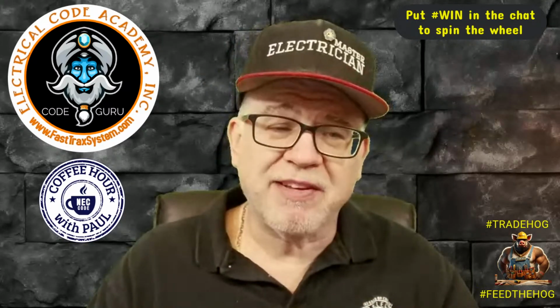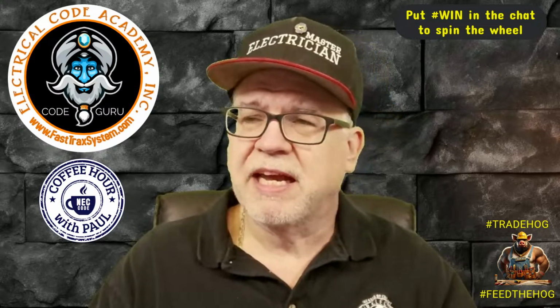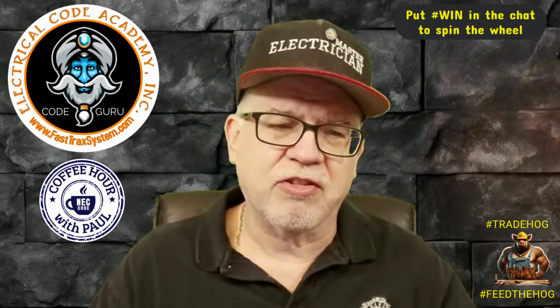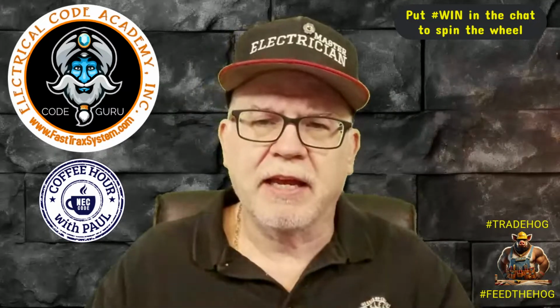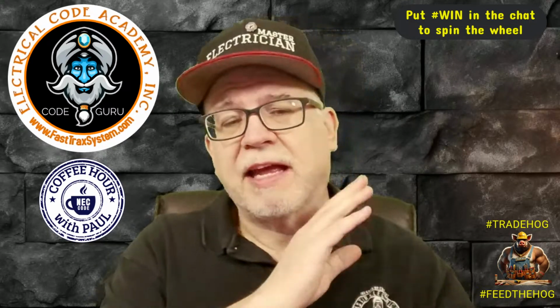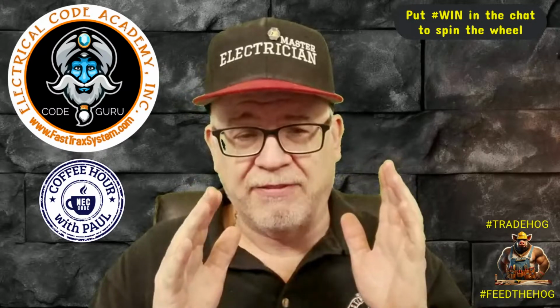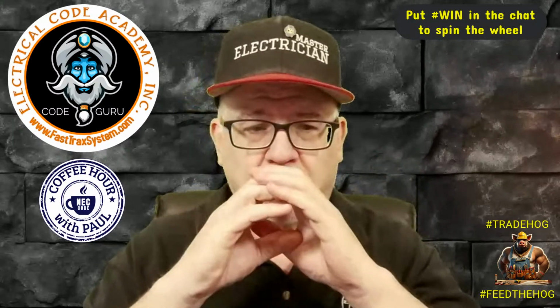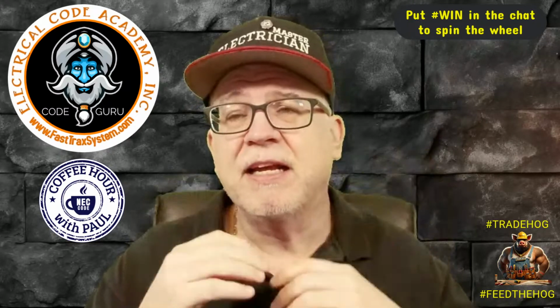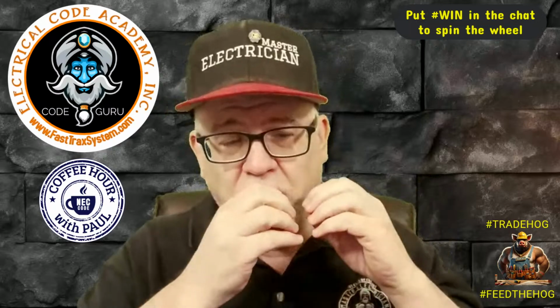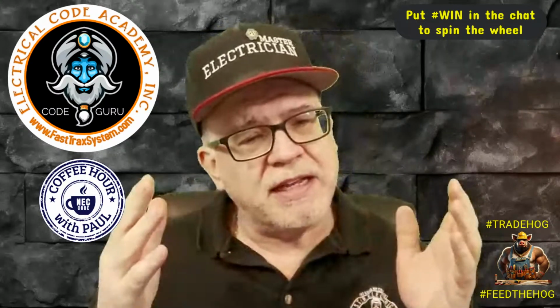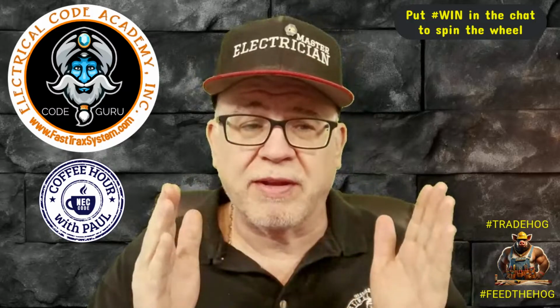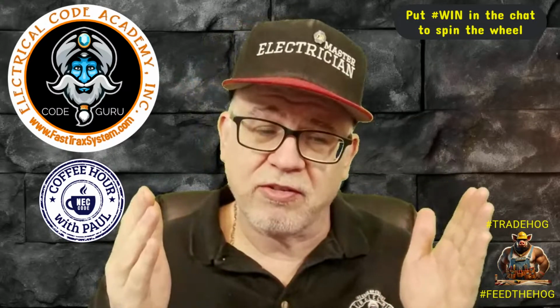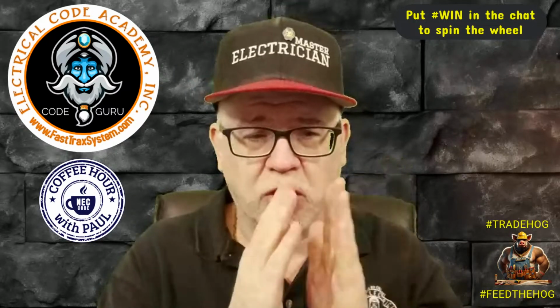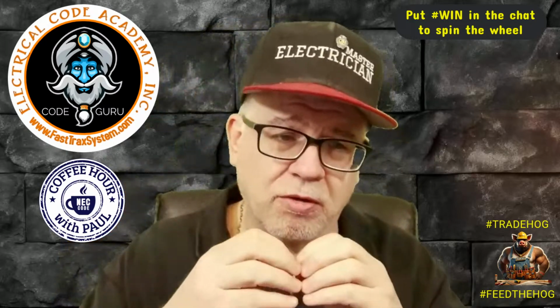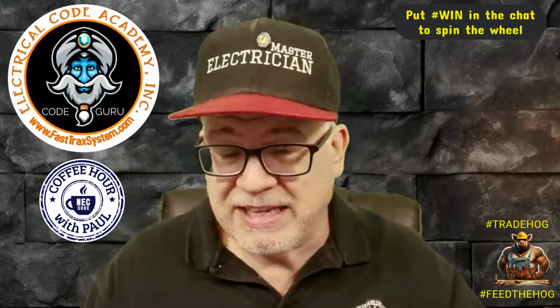Now, there are other requirements when it comes to non-metallic sheathed cable. There are bundling rules and other things you have to be aware of in the code. But at the end of the day, when you're taking cables through bored holes with thermal insulation, it's going to affect the ampacity of the conductor, because at that one point the heat can't dissipate and you create a hot spot. But again, that's with thermal insulation. Bundling is where you're running multi-conductor cables together without maintaining spacing for over 24 inches. That's not going to be the case when you go through a bored hole, because you go through one, space them out again, and go through another, space them out again. So you're not going to have that situation. But yeah, there's no fill requirement.